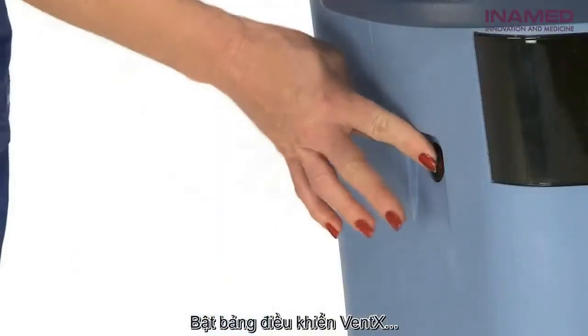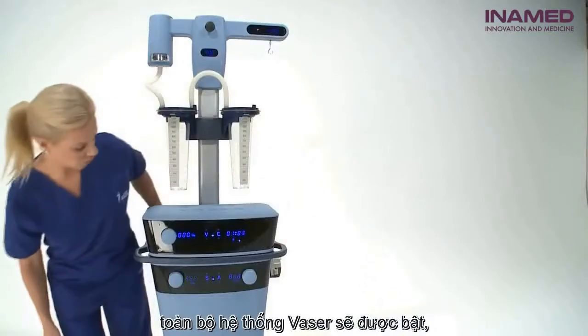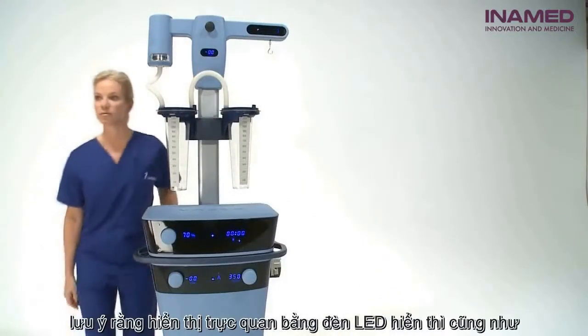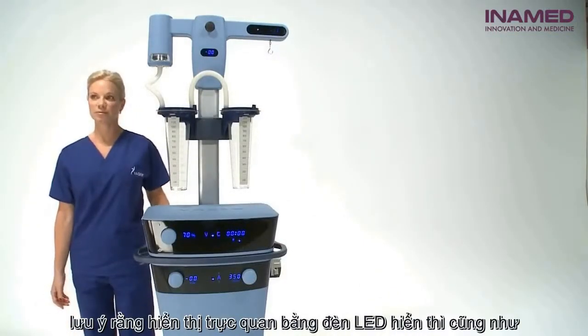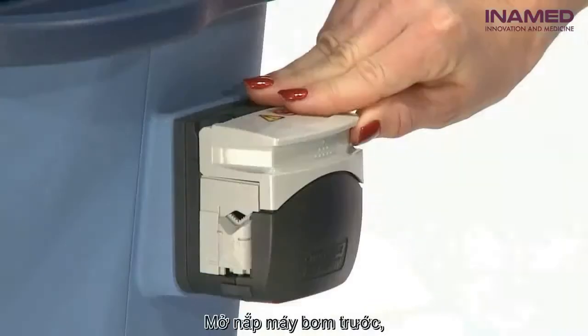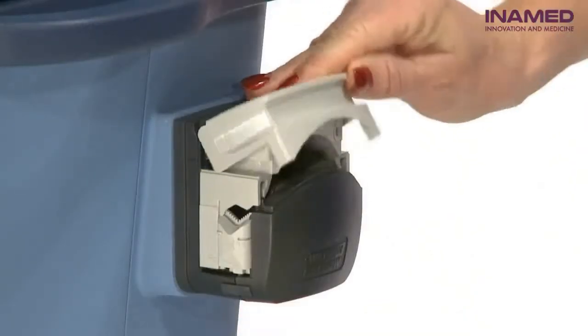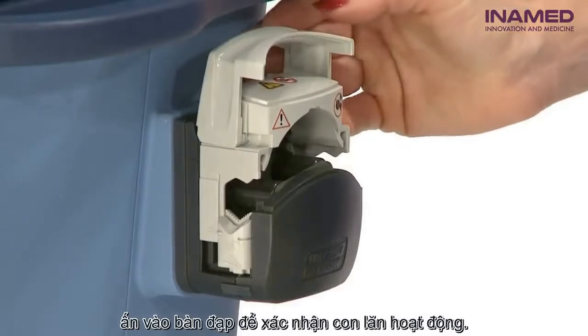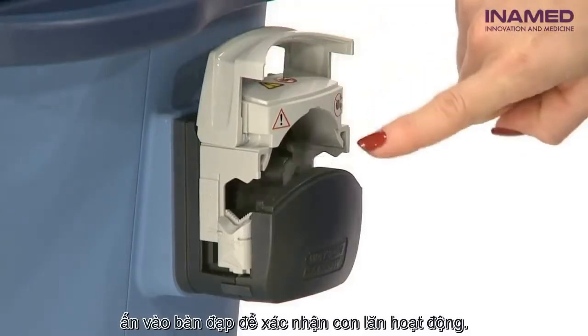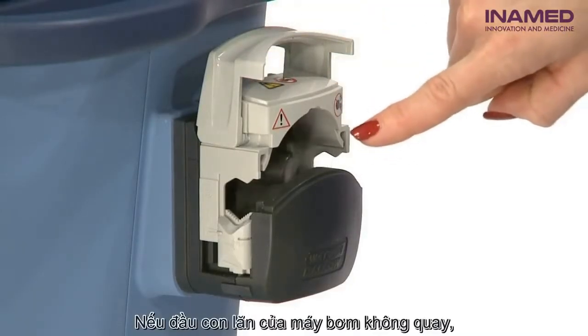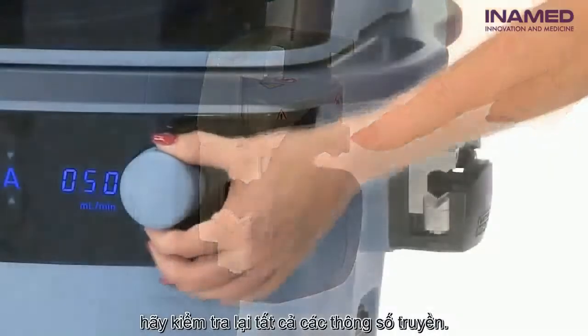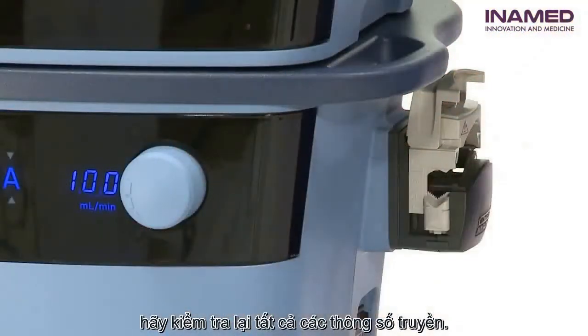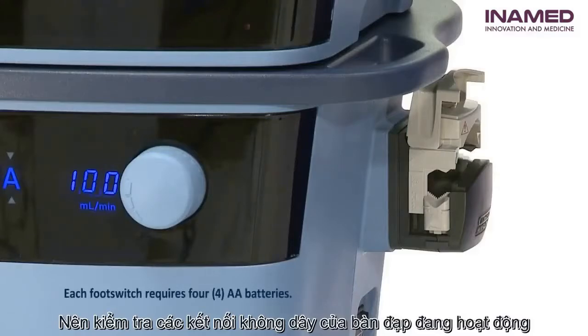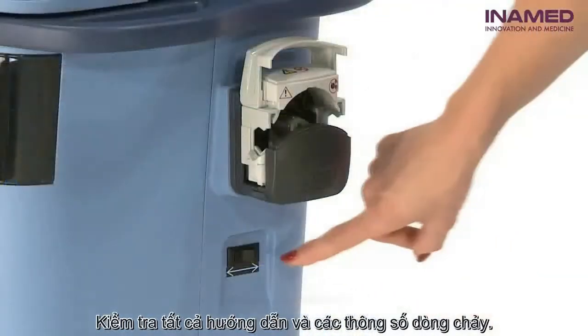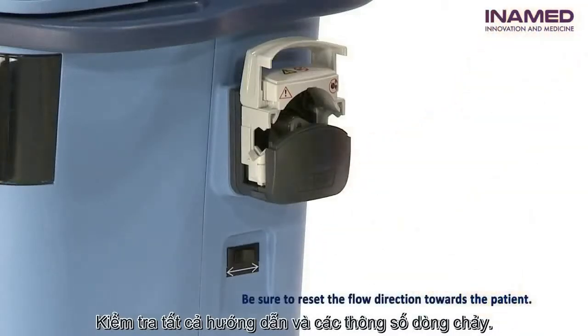Turn on the VentX console. The entire Vaser system should power on, noted by both a visual display of the LEDs as well as an auditory hum. Open the peristaltic pump head. Depress the infiltration foot switch to confirm the rollers are active. If pump head rollers do not turn, check that the infiltration rate is exactly on a number. Also check that the wireless foot switch transmitters have working batteries. Test in both directions and at all flow rates.